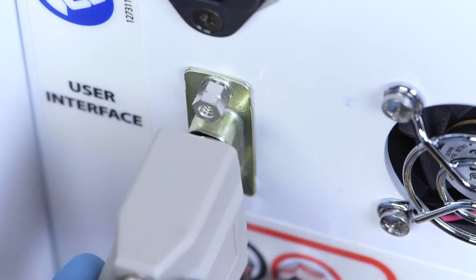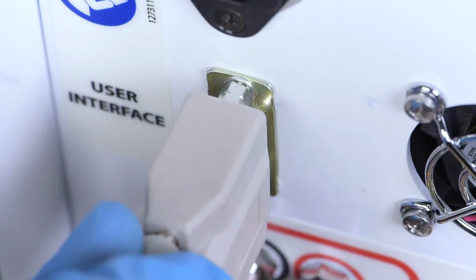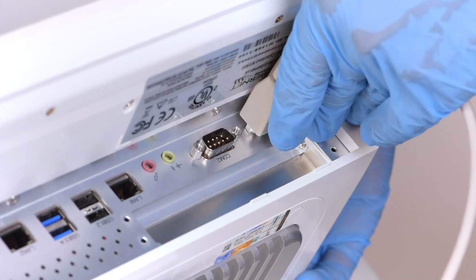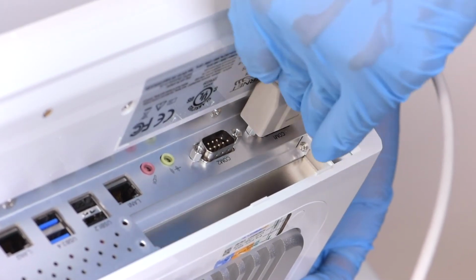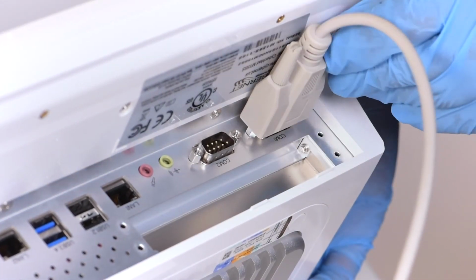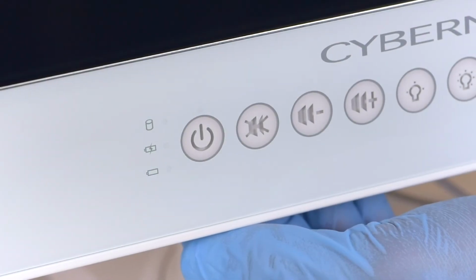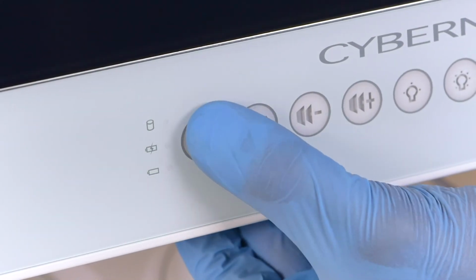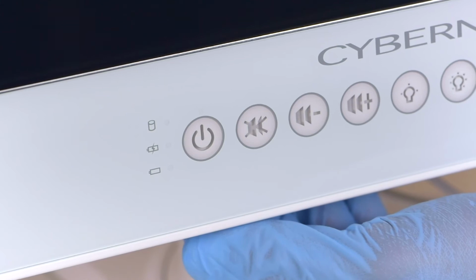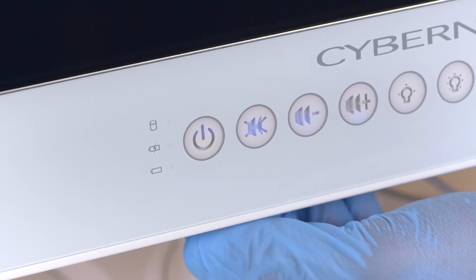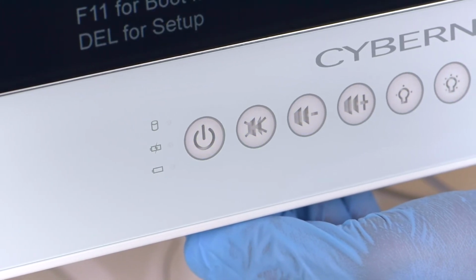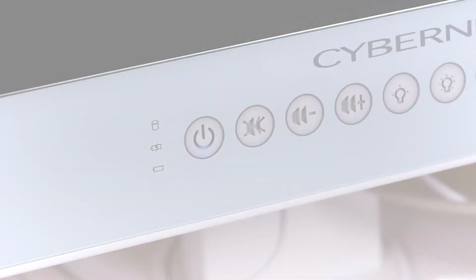Attach the serial connection cable to the back of the control room unit and the COM1 port on the user interface. Connect the power cables to the back of the user interface and turn on the UI. The RespirAct application will automatically launch on startup. You will notice that you get a system disconnected error at this time.